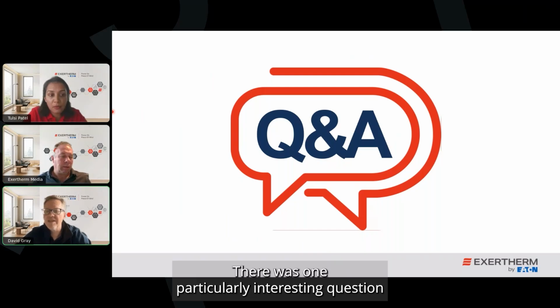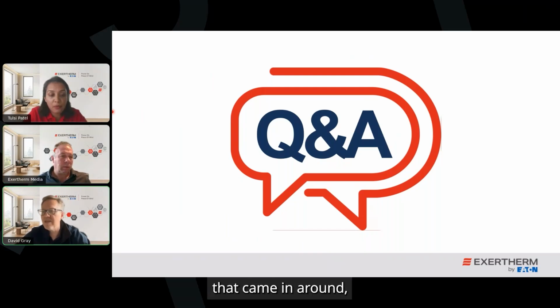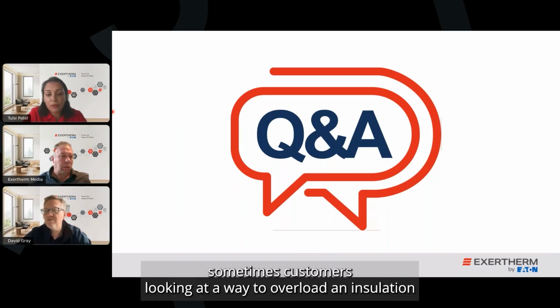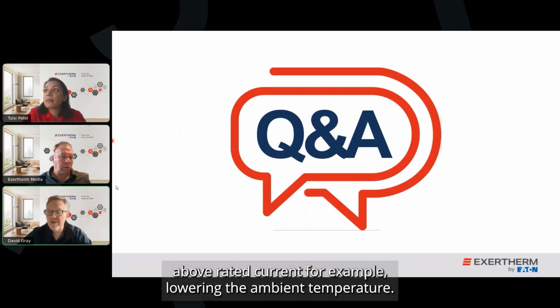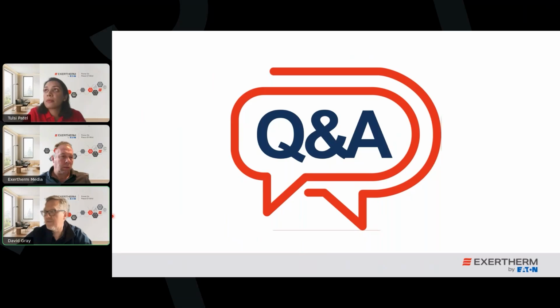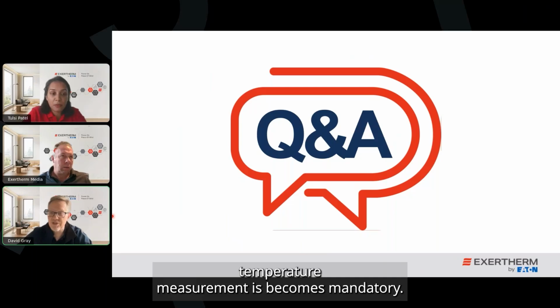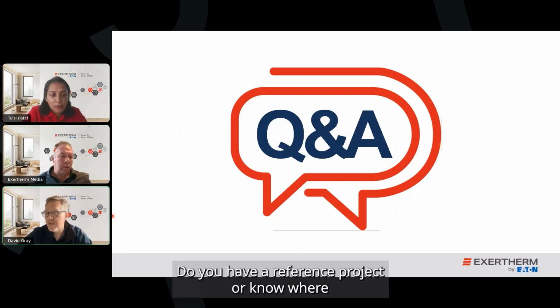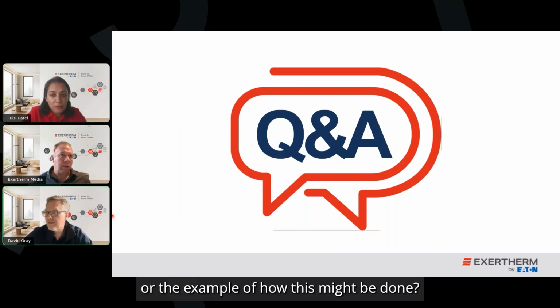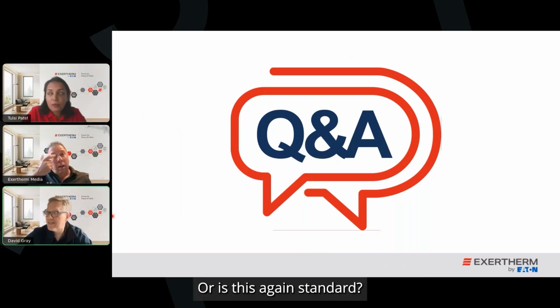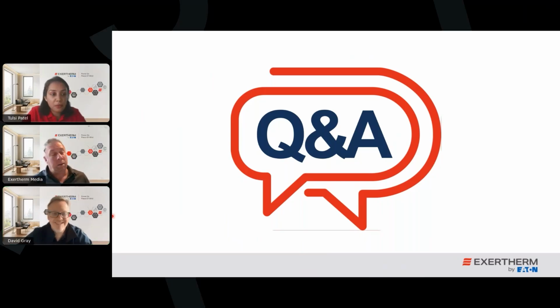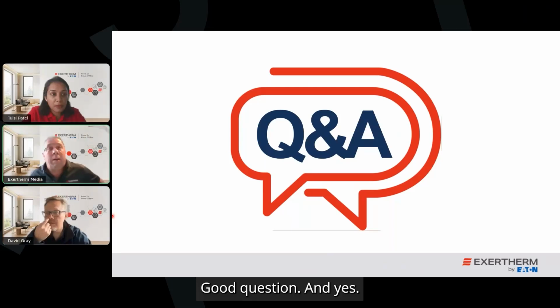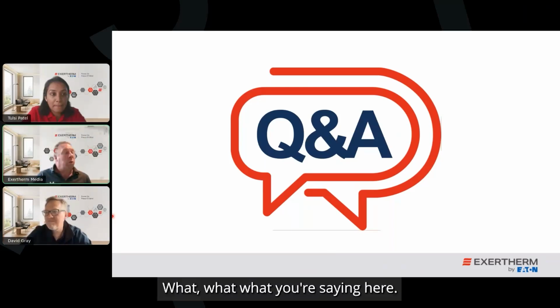There was one particularly interesting question that came in around sometimes customers looking at a way to overload an installation above rated current, for example, lowering the ambient temperature. Therefore, continuous temperature measurement becomes mandatory. Do you have a reference project or know where or an example of how this might be done? Or is this against standards? Good question, and yes, quite right, what you're saying here.